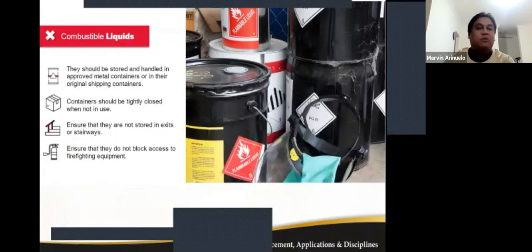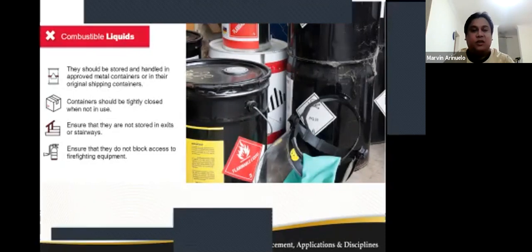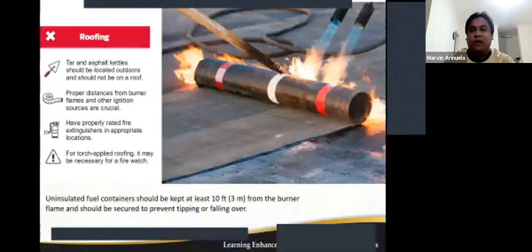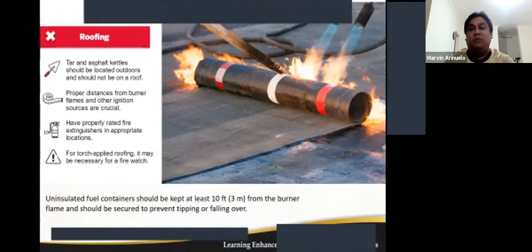Combustible liquids. Flammable and combustible liquids present obvious fire protection problems. They should be stored and handled in an approved metal container or in their original shipping container. So you cannot just simply mix up these chemicals. The container should be tightly closed whenever it is not in use, and care must be taken to ensure that these liquids are not stored in exits or stairways, and do not block access to firefighting equipment, apart from the potential hindrance to means of egress. Potential blockage of your firefighting equipment must also be taken into consideration.